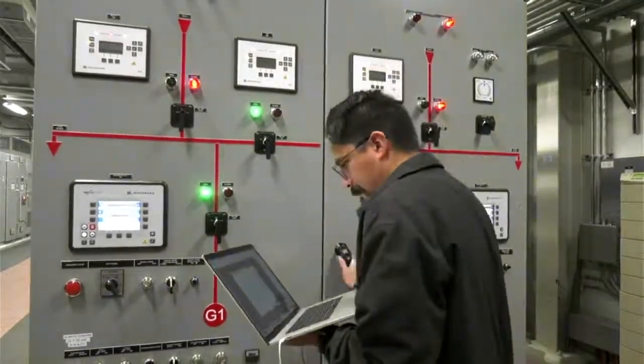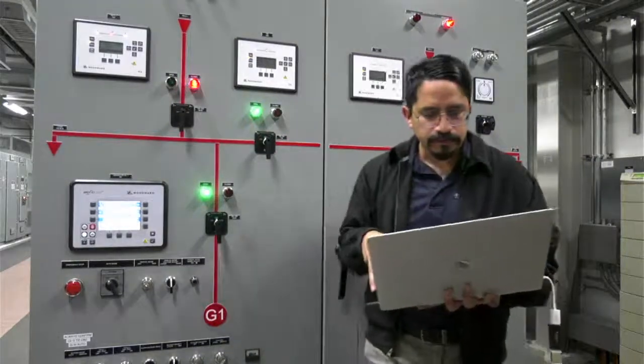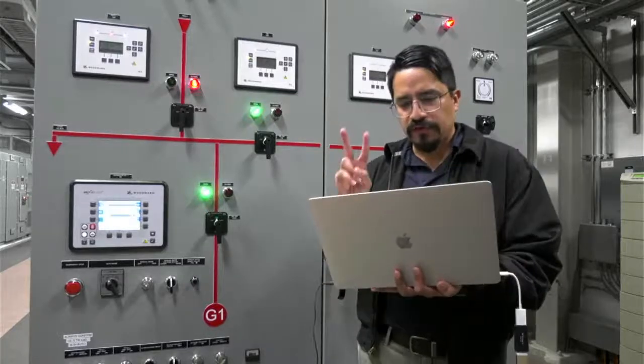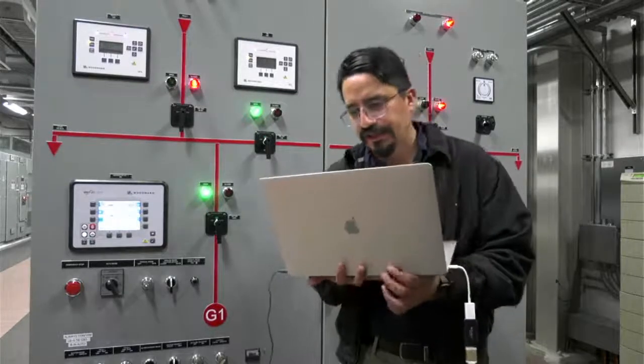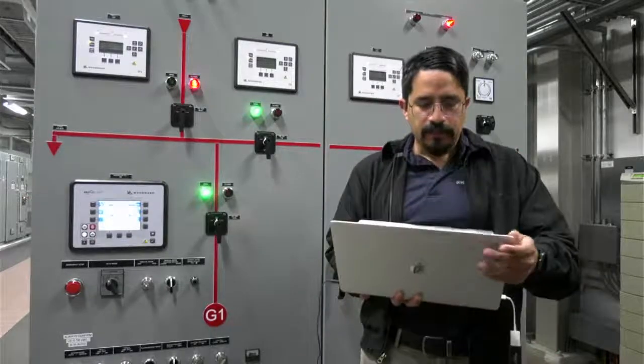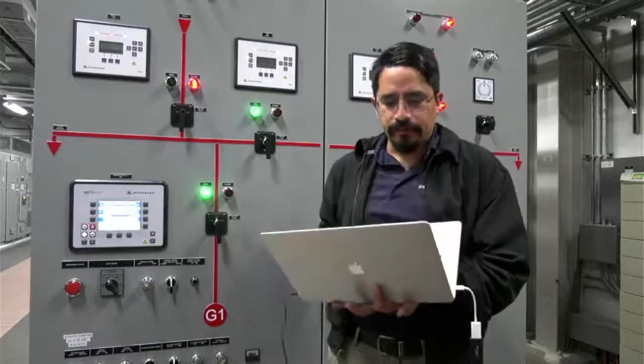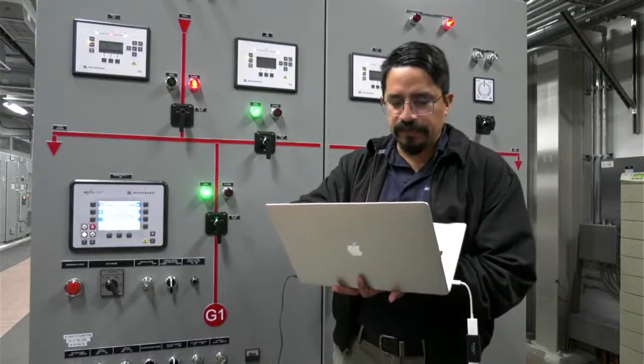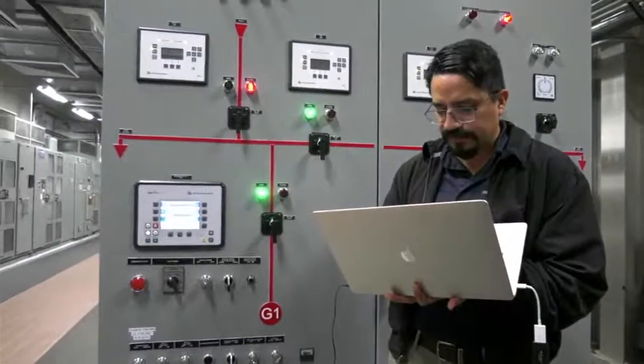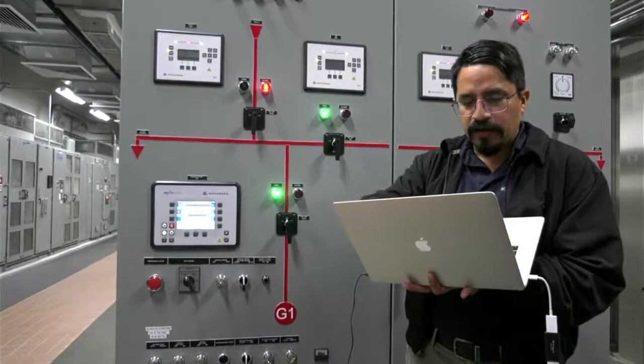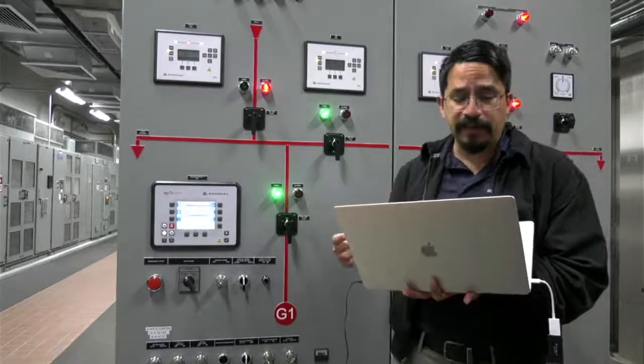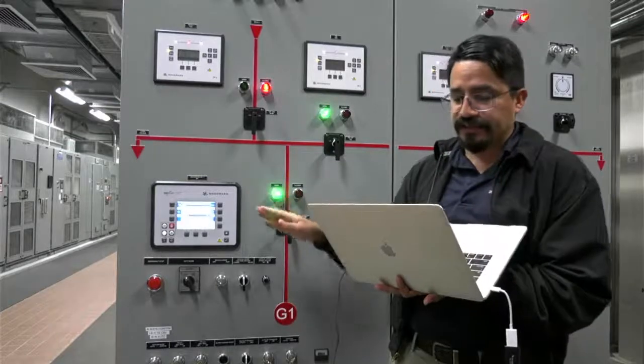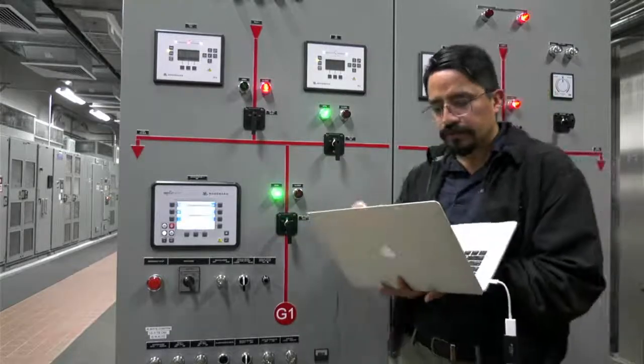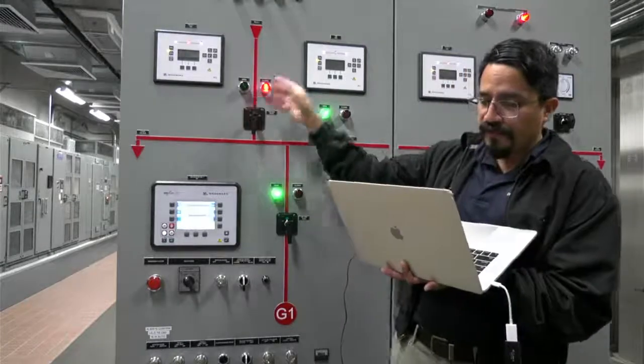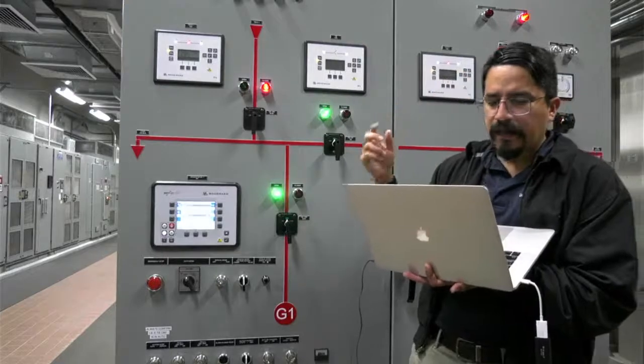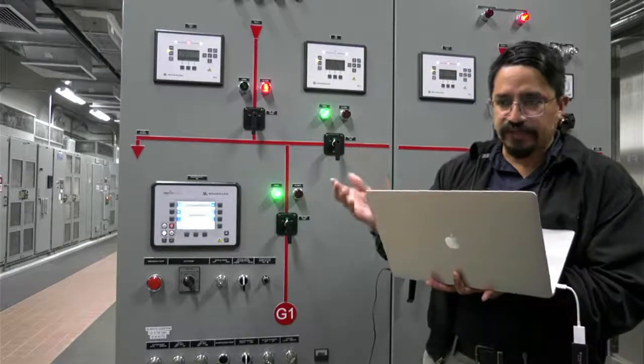Close this again, and so as I said, we have two main modes. I'm looking at sheet 26. Manual and auto. In manual, I'm going to read this back to you, so you can be on the same page and explain a little bit more. In manual, the operator has the capability to open the circuit breakers, start the emergency generators, G1 or G2, and close the main services, over here Tico 1 or Tico 2, unless there is a protection lockout.